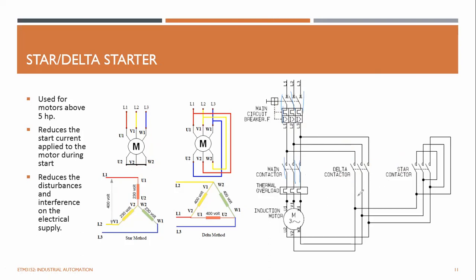Then the first thing is to run this star contactor. So someone has to press this star contactor. It closes all these contacts, which means U2, V2, and W2 are all short circuiting together. You can think about how it is short circuiting, like literally V2, W2, everything will be short circuited if you press this one. So it is short circuiting all these terminals, allowing the motor to run in this star manner.